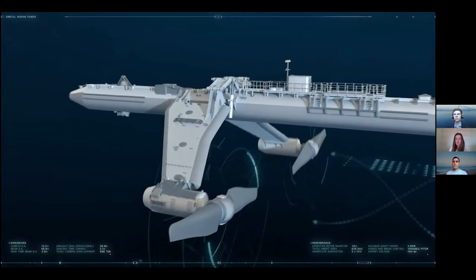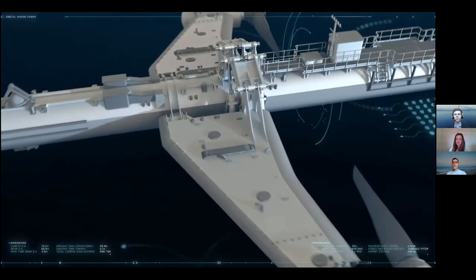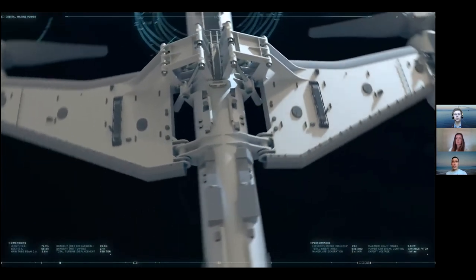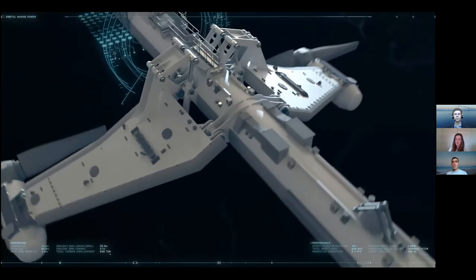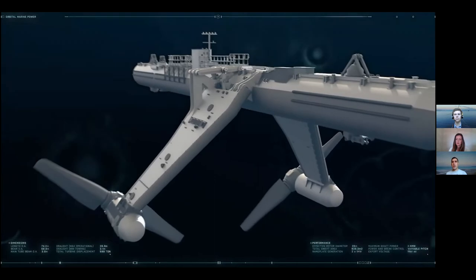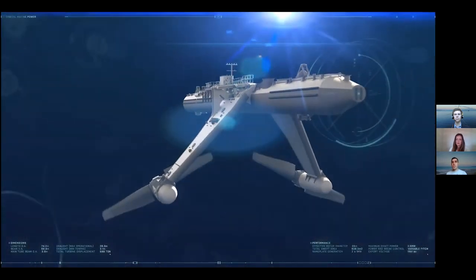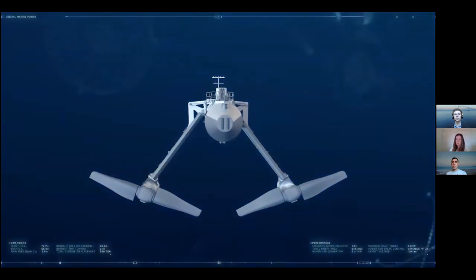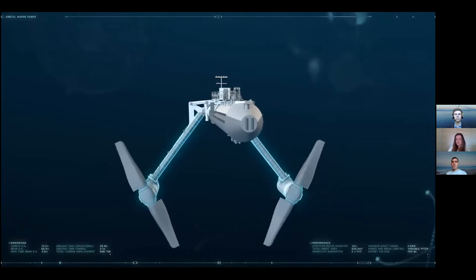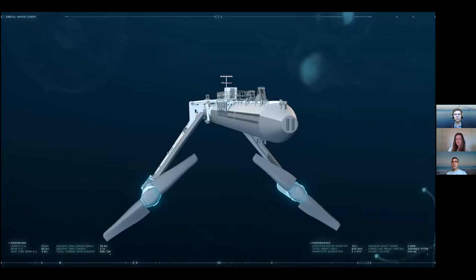Well, thanks, Andrew. And to reiterate then, how much power can be produced from this turbine? We have a nameplate rating of 2 megawatts with the O2. Actually, technically and physically, we have more like 2.25 megawatts of power generation on board. So we have 20 meter rotor diameters here. That means that the turbine reaches rated power at 2.5 meters per second. At that point, we'll be generating a little bit over 2 megawatts of power.